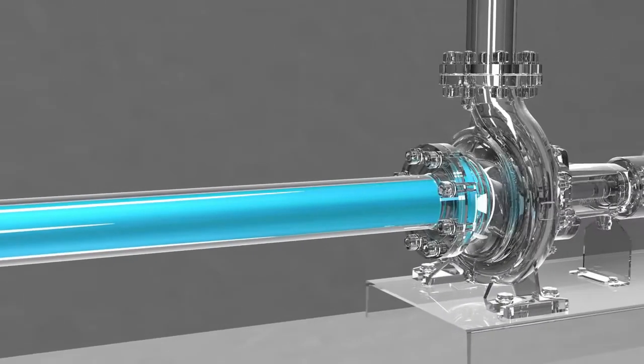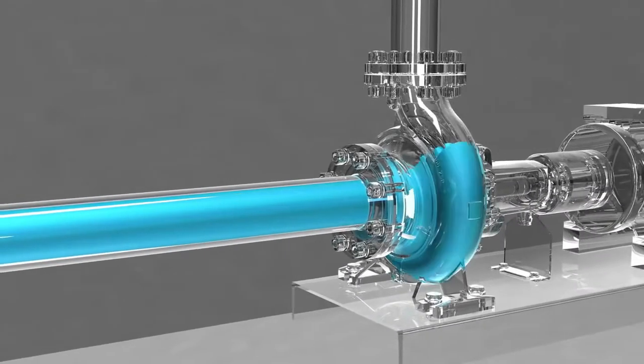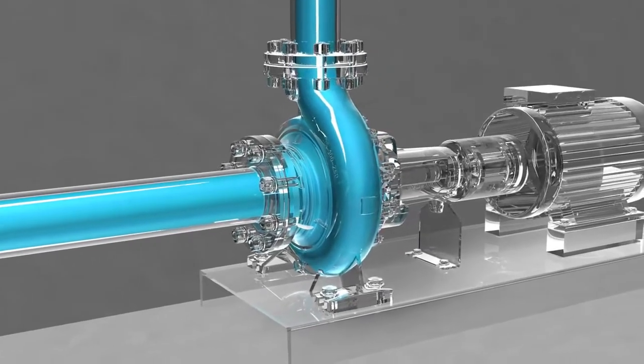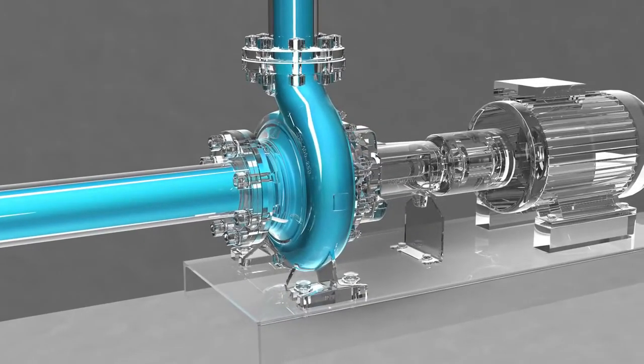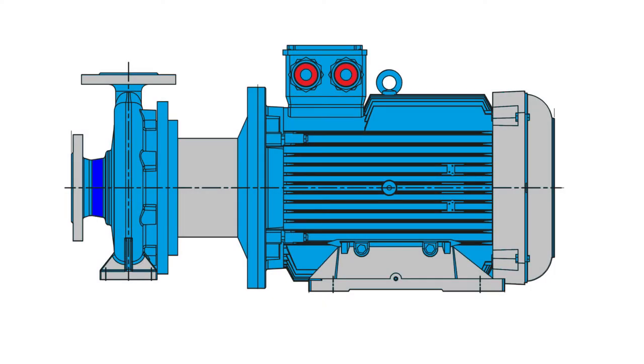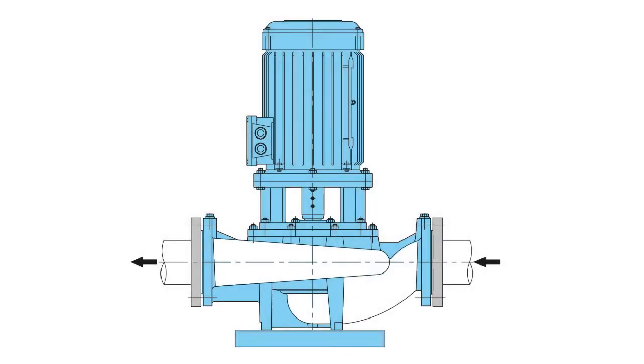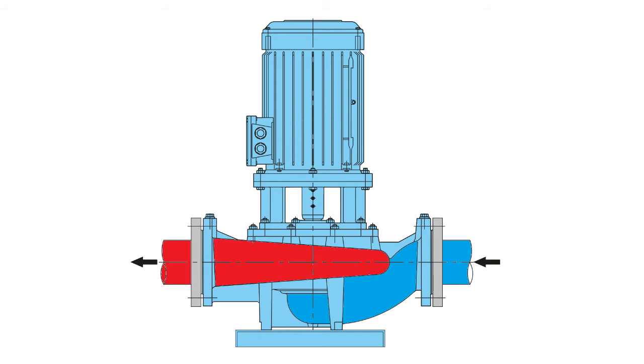Centrifugal pumps are used to transport fluids by the conversion of rotational kinetic energy to the hydrodynamic energy of the fluid flow. The rotational energy typically comes from an engine or electric motor. They are a subclass of dynamic axisymmetric work-absorbing turbo machinery. The fluid enters the pump impeller along or near to the rotating axis, and is accelerated by the impeller, flowing radially outward into a diffuser or volute chamber, from which it exits.